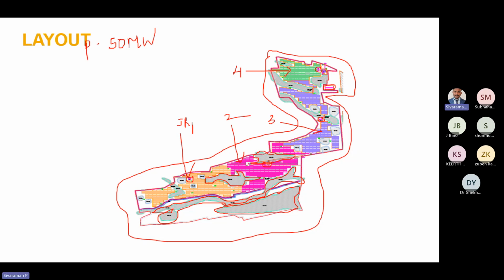So, in simple words, we have to design the solar PV system for 50 megawatt at the grid interconnection point, or POC, point of connection, or POI, point of interconnection, or PCC, point of common coupling. At that point, we have to maintain 50 megawatt power. So for that, what do we have to do? We know how much power we have to maintain at the interconnection point, that is 50 megawatt.